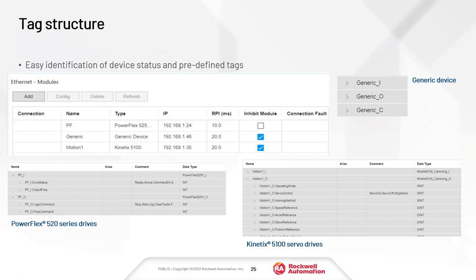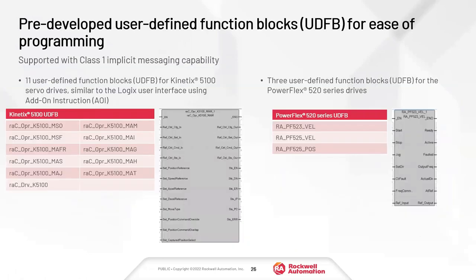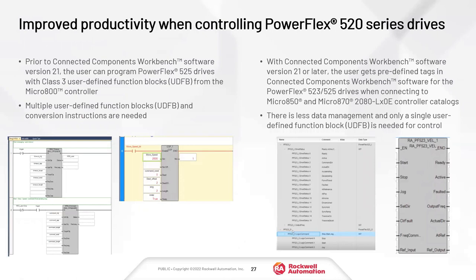As we add these devices, a tag structure gets created in our global tags in the controller. There are also pre-developed user-defined function blocks — UDFBs — for the PowerFlex 520 and Kinetix 5100 drives. These blocks interface with the drive using the tags that were created. Prior to version 21, communication to a drive was Class 3 with a user-defined function block; now starting in version 21 we have Class 1 capability with the enhanced UDFB.